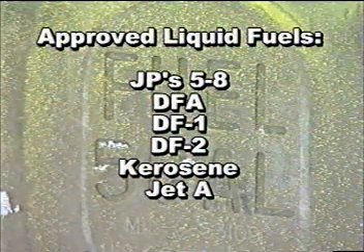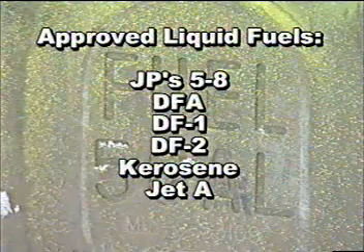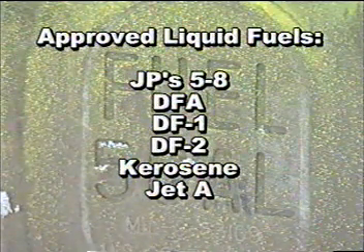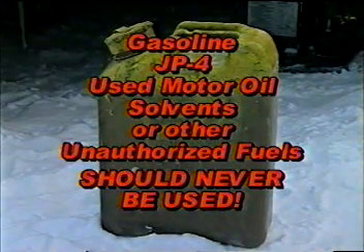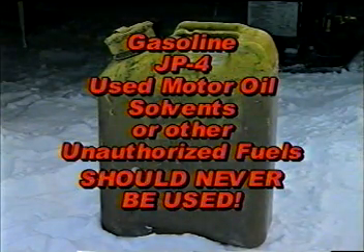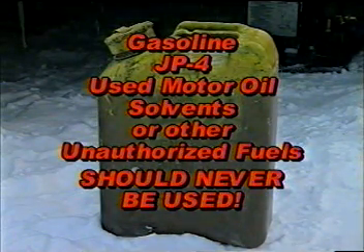Approved liquid fuels for use with the SHA are JP 5 through 8, DF-A, DF-1, DF-2, kerosene, and Jet A. Approved solid fuels are wood and coal. Gasoline, JP-4, used motor oil, solvents, or other unauthorized fuels should never be used. Using unauthorized fuels will create a fire danger and potential for explosion.